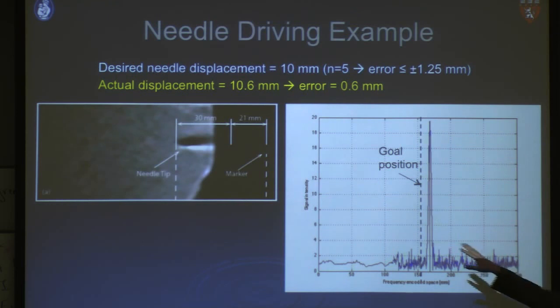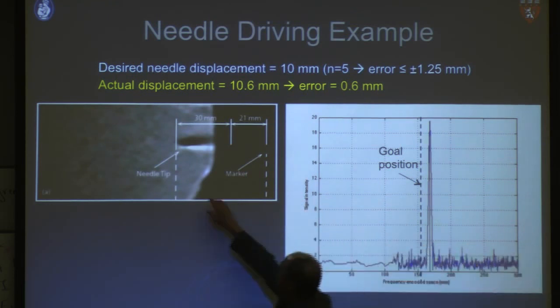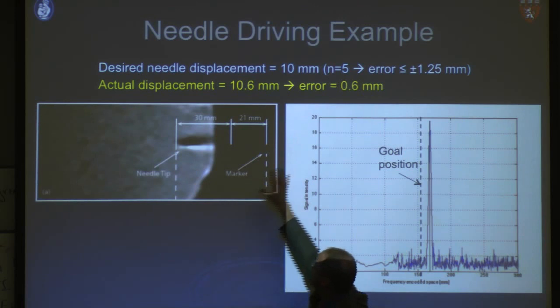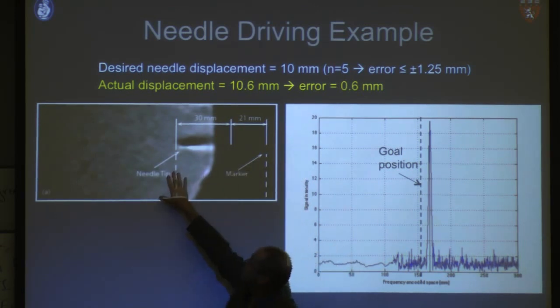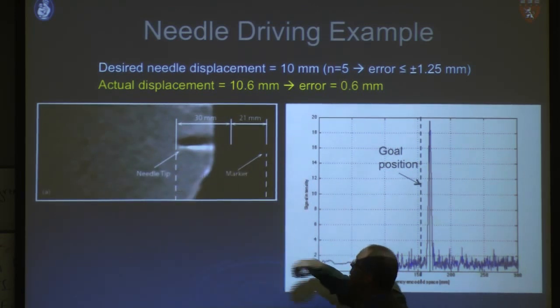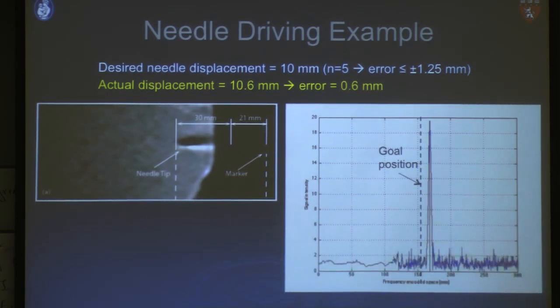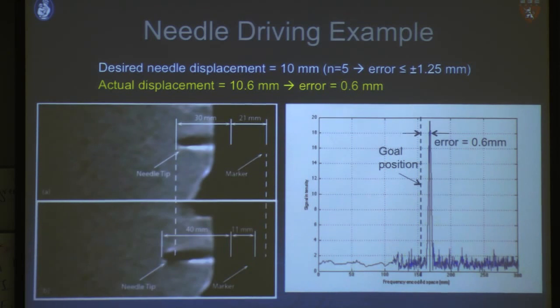Let me show an example: this was driving a needle in. This is the before image—you can see the needle tip. Even with our actuator here, it doesn't obscure the image of the tissue at all, so it's compatible. We want to advance the tip 10 millimeters, so we turn it on. It monitors how far it has to go, and bang, it stops. The error was about 0.6 millimeters, since the resolution is a little over 1 millimeter. So we proved that even in this open loop commutation, you can do things like needle driving.